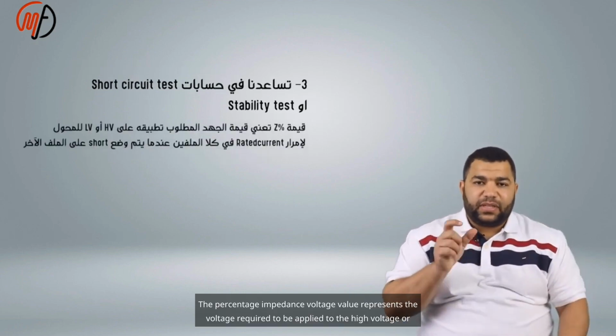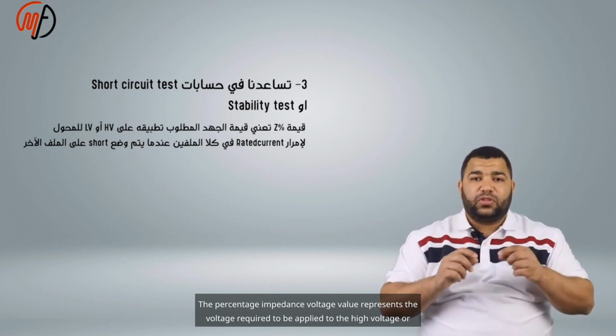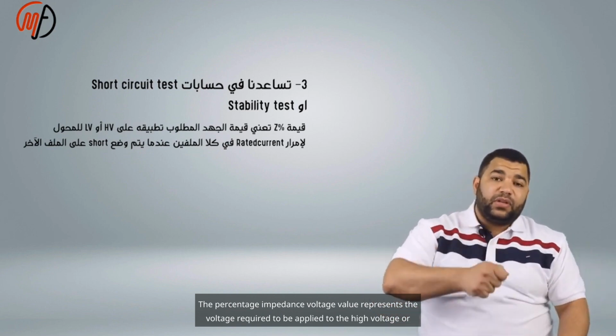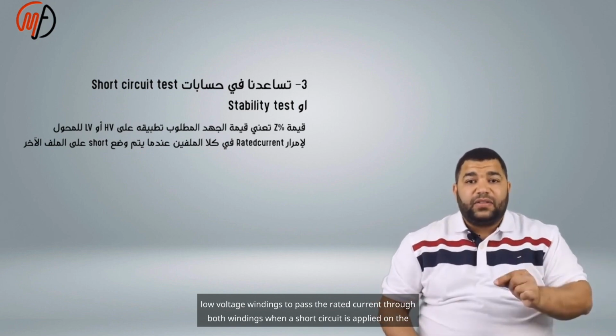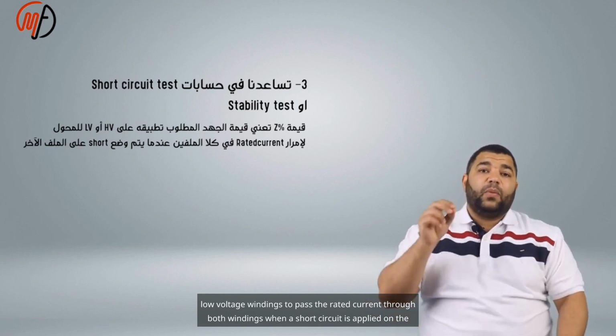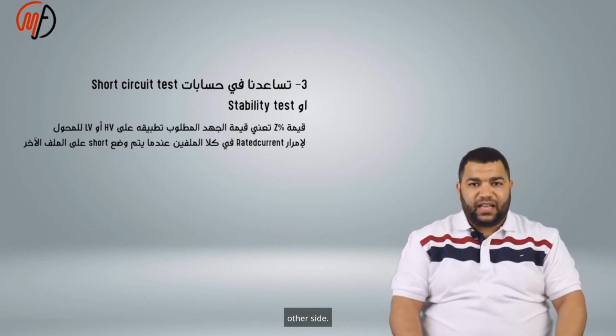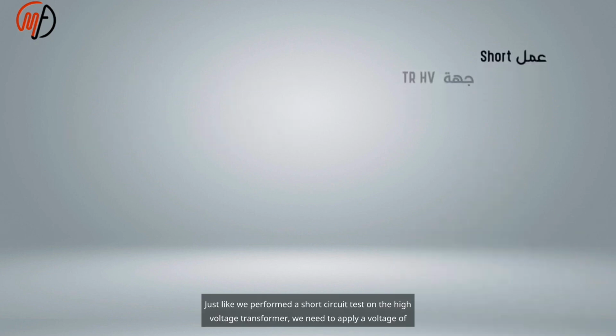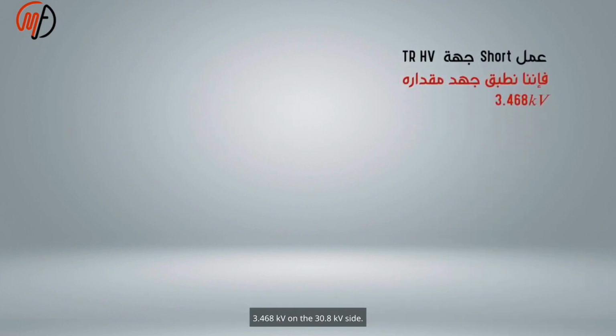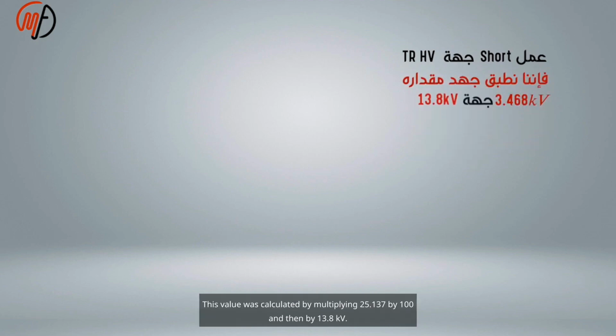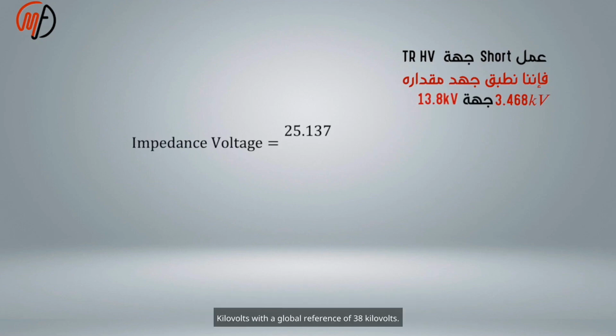The percentage impedance voltage value represents the voltage required to be applied to the high voltage or low voltage windings to pass the rated current through both windings when a short circuit is applied on the other side. Just like we performed a short circuit test on the high voltage transformer, we need to apply a voltage of 3.468 kV on the 13.8 kV side. This value was calculated by multiplying 25.137 by 100 and then by 13.8 kV. The voltage is 13.8 kV.